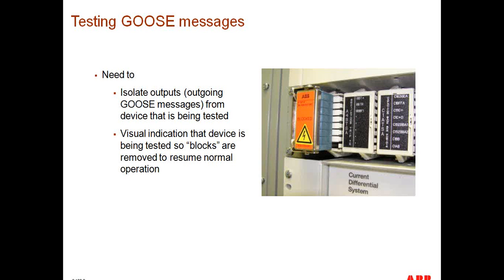And then the second requirement is that there needs to be visual indication that the device is being tested so that the blocks can be removed to resume normal operation. And here I have a picture of a test switch that we use to block trip and close circuits. And again, by using this, you're still allowed to measure the operation of the output contacts of your relay to be able to perform your testing.